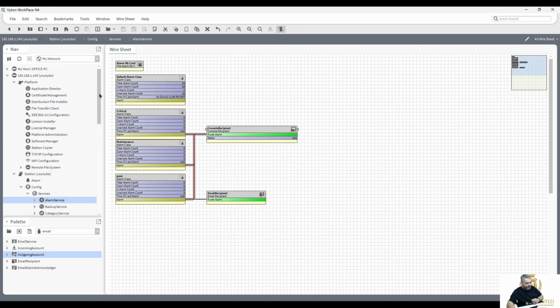So that's it for that video, and you might have known about that, you may not have known about that, but it's just something extra to add in, just in case you're communicating via FOXS on port 4911 and then you end up a year later not getting communication after a system is rebooted, you know where the issue is going to be.